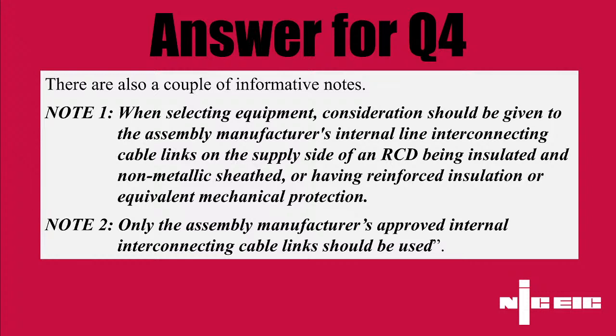Okay, so we've got another one. What about on a dual RCD distribution board that has a single insulation on the RCD links? This would need 100 milliamps at the head. Selection is key and keeping the tails as short as possible.